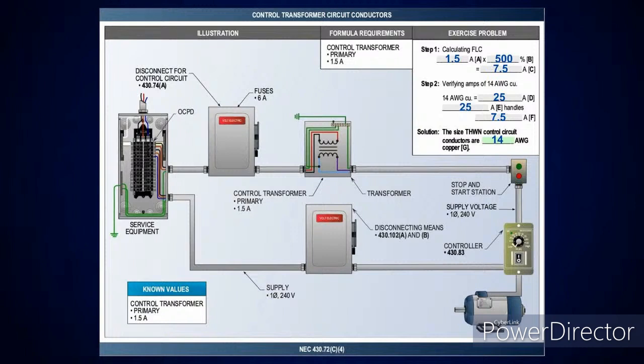Hook 'em horns. Now this is a control transformer at 1.5. When you go over and look at 725 point something, I'm trying to remember the exact section over there, but anyway, they allow you to go to 300%. But when you come over here and look at 430.74, they allow you to go all the way up to 500%. Okay. Right. And they're telling you here what I can have. So if I took 1.5 at 500%, it's going to give me 7.5. They're basically just telling you that number 14 will handle that 7. So even if I did it at 300 or 500, it would still hold the load that's there.